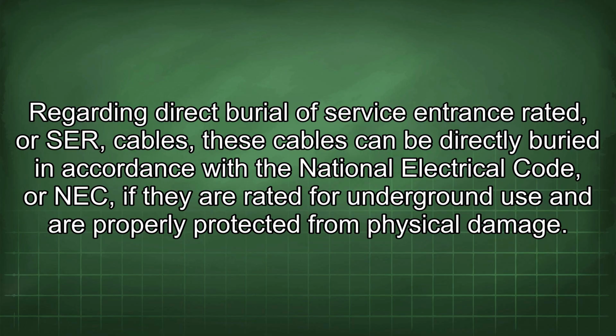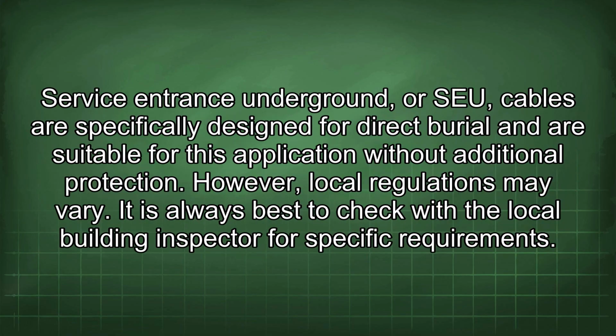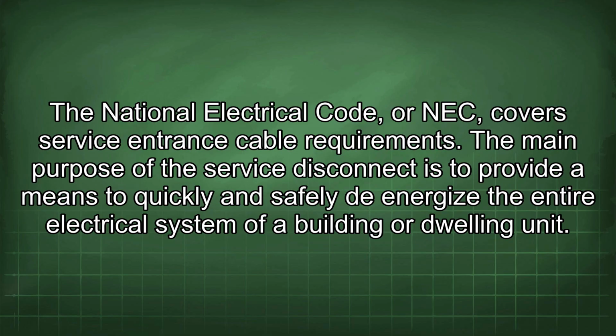Regarding direct burial of service entrance rated, or SER, cables, these cables can be directly buried in accordance with the National Electrical Code, or NEC, if they are rated for underground use and are properly protected from physical damage. Service entrance underground, or SEU, cables are specifically designed for direct burial and are suitable for this application without additional protection. However, local regulations may vary. It is always best to check with the local building inspector for specific requirements. The National Electrical Code, or NEC, covers service entrance cable requirements.